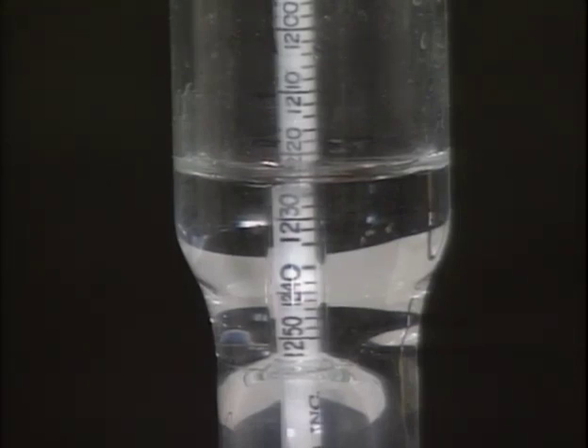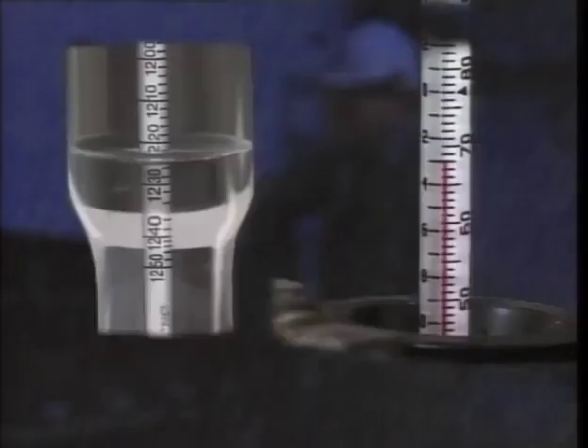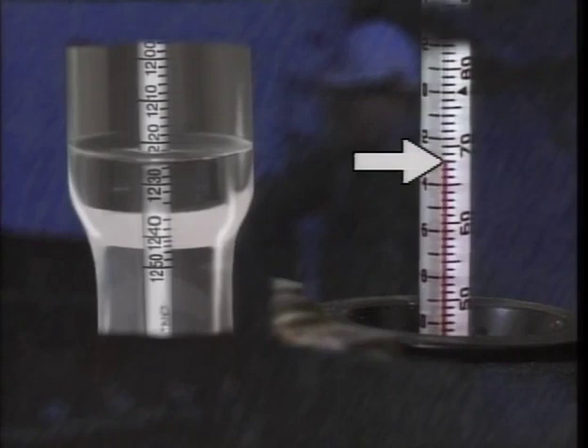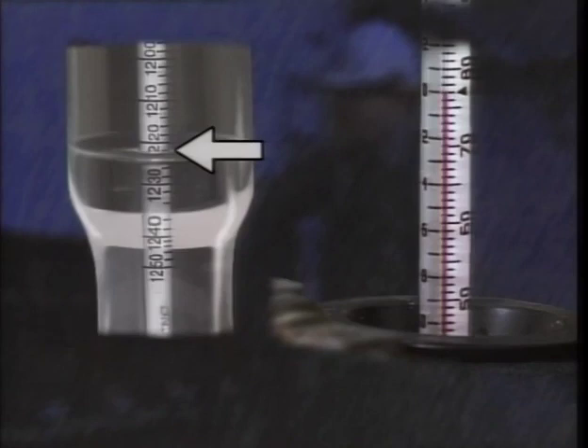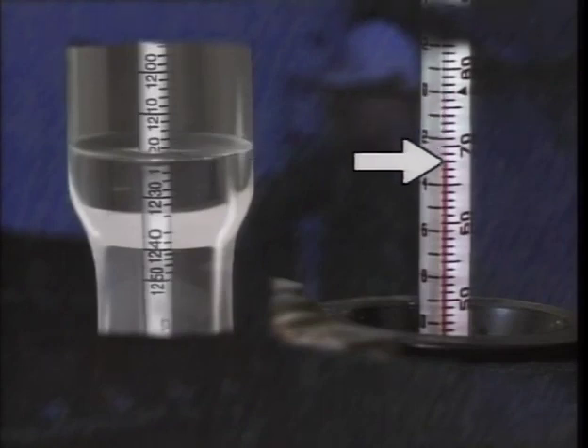This is not necessarily the value that's recorded. Specific gravity is affected by temperature, so the reading may need to be corrected for the temperature of the electrolyte. Electrolyte temperature may be checked using a cell thermometer. Here the cell temperature is 68 degrees Fahrenheit. When electrolyte temperature increases, its specific gravity decreases because warmer liquids are less dense than cooler liquids. When the temperature decreases, the specific gravity increases.